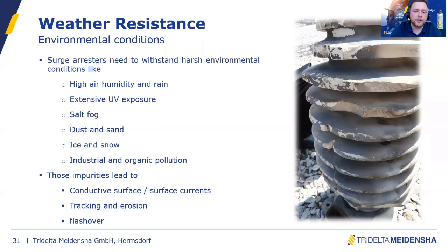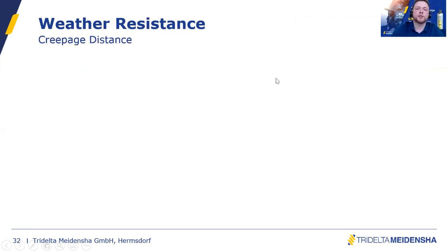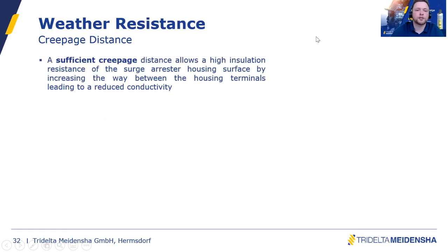And of course, we have a high risk of flashover when the surface is humid and polluted and current is flowing. And perhaps it's possible that this current ignites an arc across the surge arrestor housing. So this is the risk, and we have to cover this. We have to consider this by using this typical shed profile of the surge arrestor.